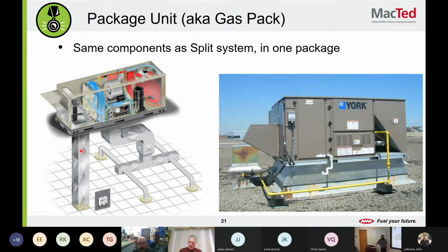But yeah, for duct cleaning, more often than not, you're going to be looking more on the return side because that's going to be pre-filtration. And so you're just pulling in whatever's inside your room. It's going up into that ductwork and it's not getting filtered. So usually if you're looking at a system, your return duct is going to be the one that gets dirtier. But again, for cleaning, you're absolutely right. It is possible to do damage if proper care is not taken. And again, usually there's some form of isolation on that duct from the package unit to prevent such things.